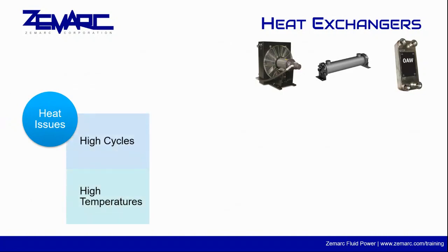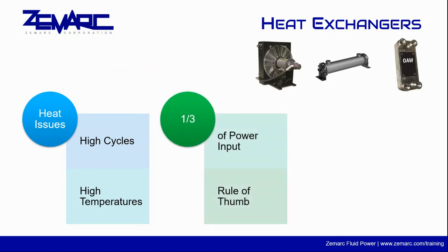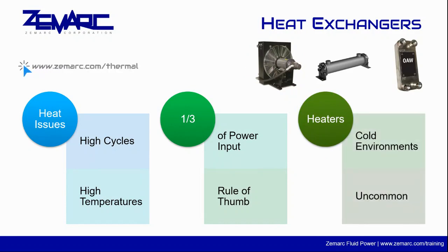Heat exchangers can be installed in systems if there's concerns about your fluid temperature. Coolers are often used when a hydraulic power unit is in any situation where large amounts of heat will be generated, such as long periods of cycling. A good rule of thumb is to size coolers so that the heat removed is about 1/3 of the power input to the system. Heaters are less commonly used and are placed in hydraulic power units located in cold environments.